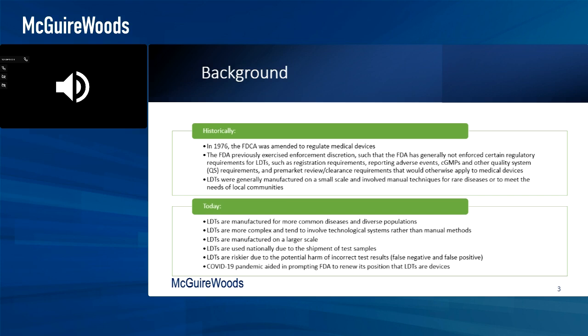And the change has really been that we've seen LDTs go beyond this concept of being used in a small clinical setting in a hospital lab to being part of large-scale operations for really complex diseases, being manufactured in facilities. Yeah, they're going to a lab. Yeah, they're getting read in the lab, but they're really starting to look more like IVDs according to FDA.